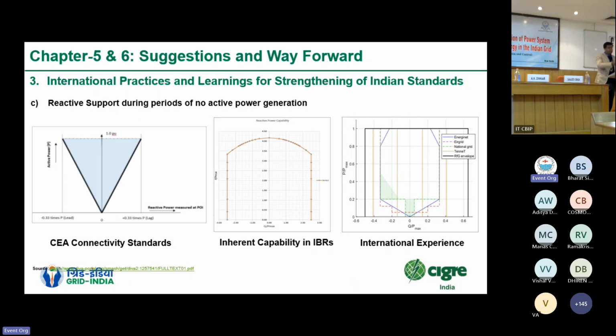Again, next is the reactive support mentioned in our standards. We can see this is a simple triangular curve with a requirement of 0.95 power factor lag to 0.95 power factor lead. So plants have limited their response up to this level only. But as we know, at lower output levels, plants are capable of exchanging more reactive power than that, and certainly an added margin would help us in operating our power system more efficiently. So we can see the inherent capability available in the curves given on the right, and there is a possibility of tapping that extra reactive power available in the RE plants in our day-to-day operations.